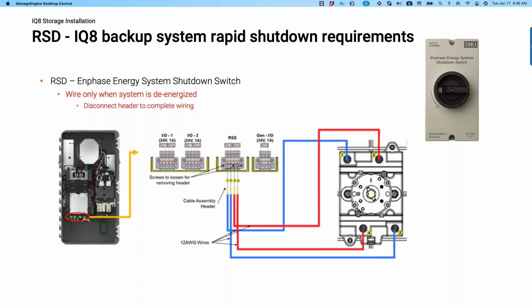Also, there is a header, all right, and that header gets pulled out. The header actually has these terminals in it. A good safety precaution is to pull the header off, wire all these wires into the header, and then plug the header back in after you've landed all the wires. So 2 things: wire this when it's de-energized. The second is pull the header off and put the wires in.